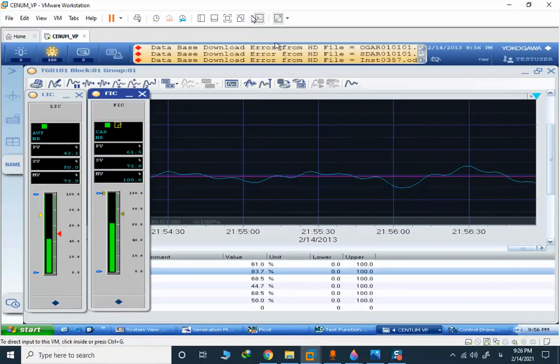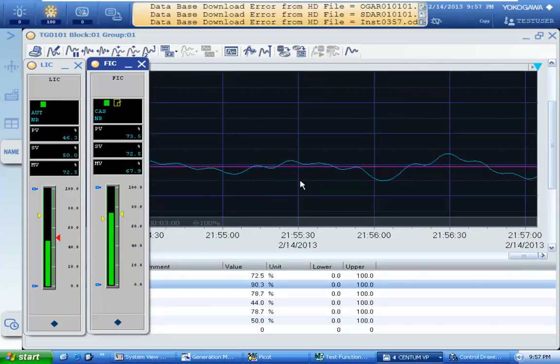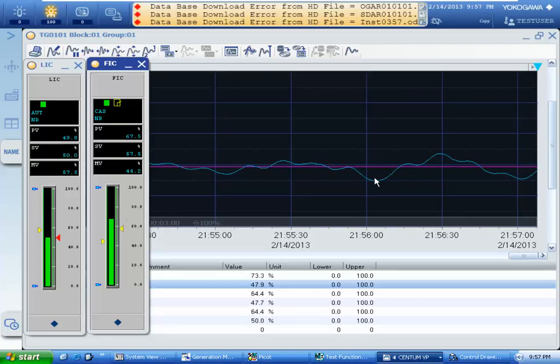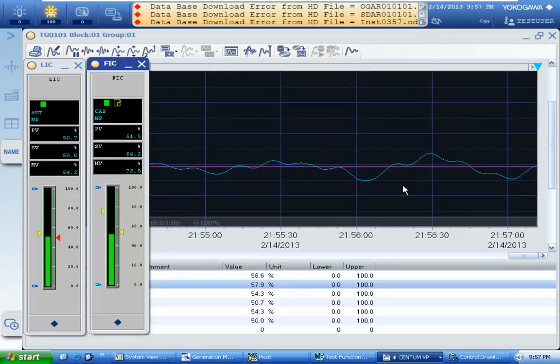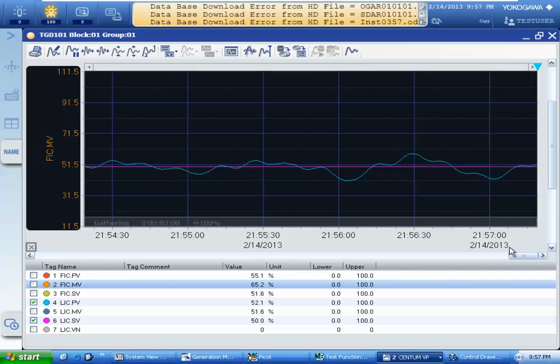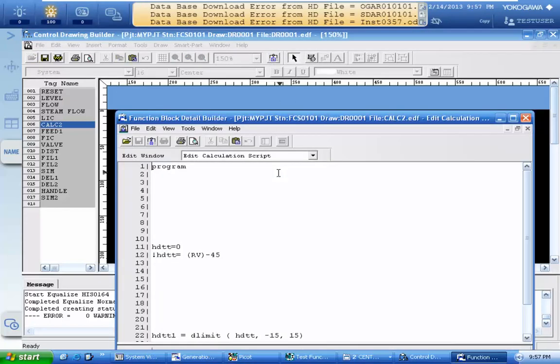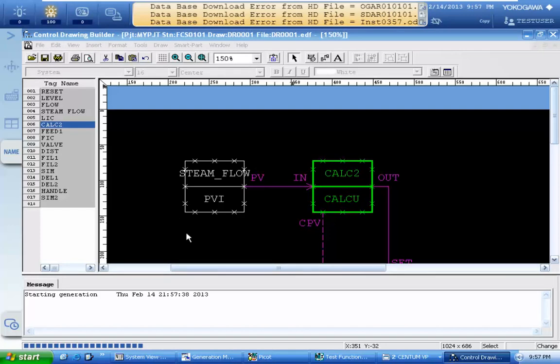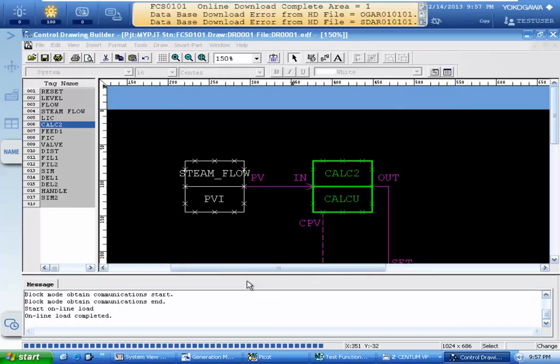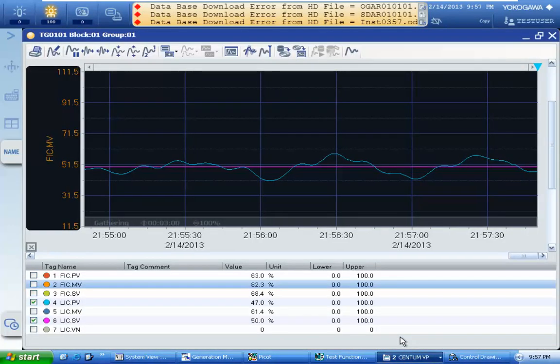You can see that the level — the amplitude of oscillation has increased, and the previous control with feedforward enabled is much more desirable behavior. I will enable this feedforward function again and we will see the positive response. It is possible to enable and disable the feedforward function in CentumVP and the output improvement is clear.